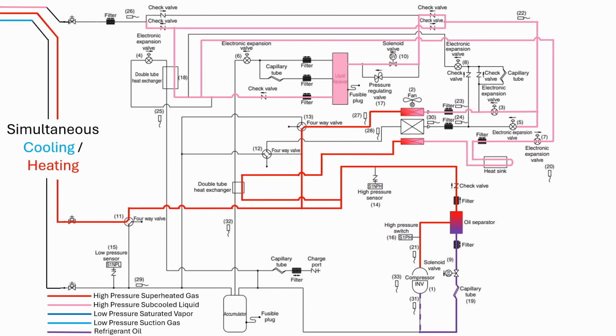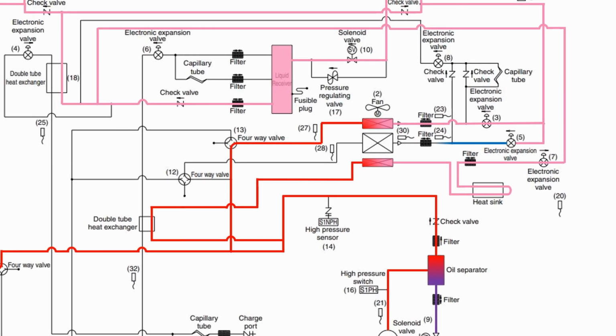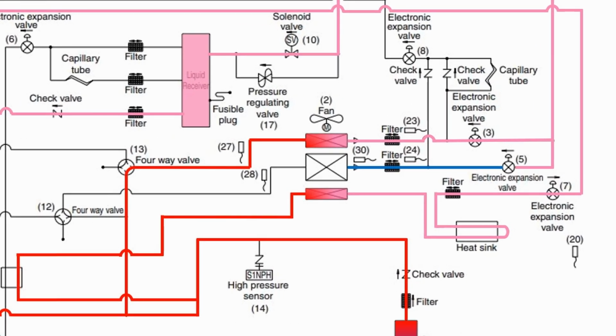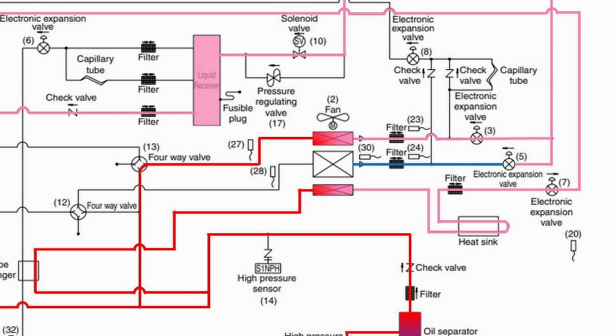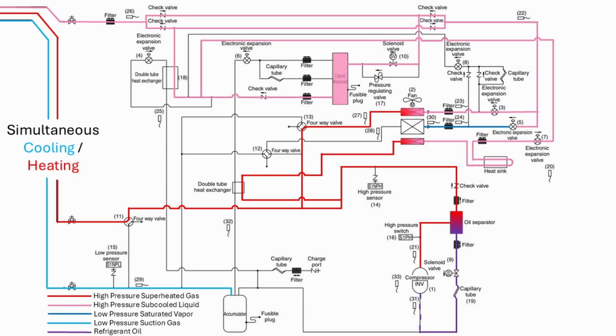The refrigerant leaves the indoor branch selector boxes and is sent back to the outdoor unit on the liquid line and the suction line. The suction line enters the outdoor unit and is routed to the accumulator. The liquid line enters the outdoor unit and is routed through a series of check valves to meet up with the liquid refrigerant from the liquid receiver and sent to the indoor units that are calling for heating. The liquid refrigerant en route to the outdoor coil passes through an expansion valve, experiencing a pressure drop and changing the state of the refrigerant to a saturated vapor.